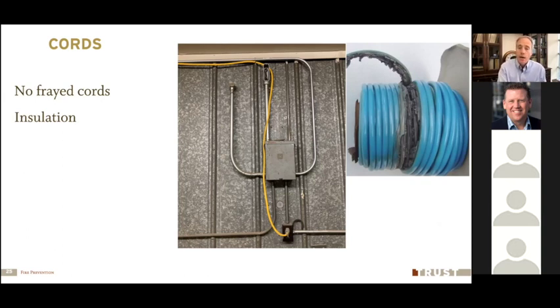So if you've got a power strip and you've plugged in a bunch of different equipment, maybe a space heater or a microwave oven and some other tools, and the combined wattage of those pieces of equipment is greater than 1800 watts on a 15 amp circuit, then you're running the risk of overloading that circuit. And if there's a fault somewhere in that wiring, the wiring could melt, spark and cause a fire. On a 20 amp circuit with 120 volts, you're looking at a maximum of 2400 watts.